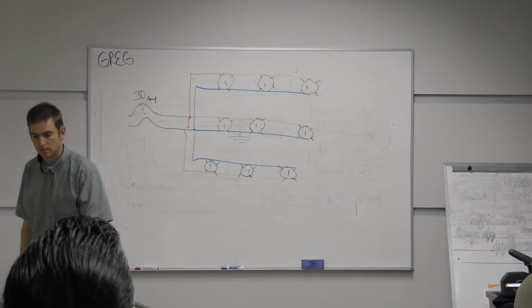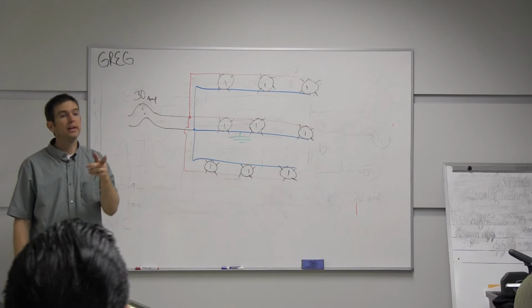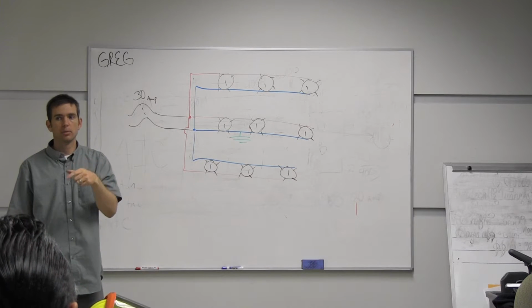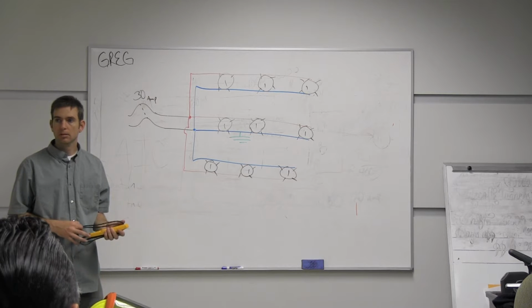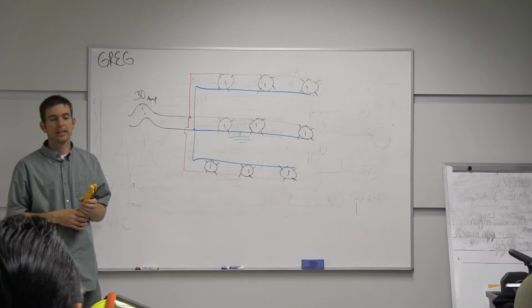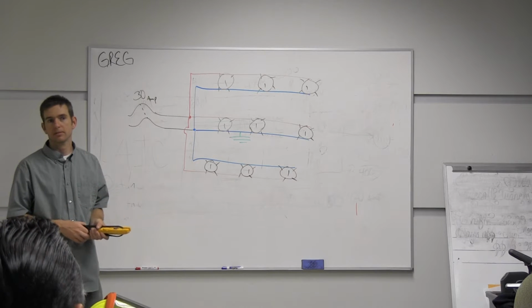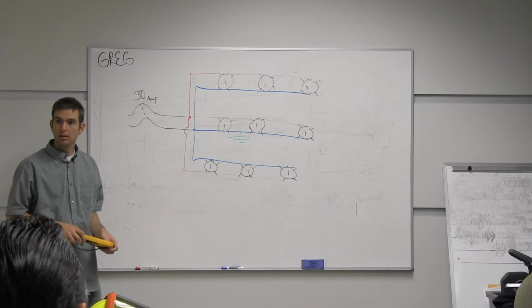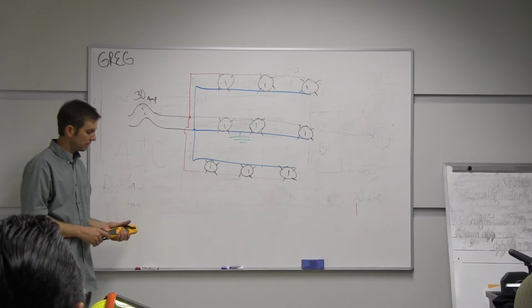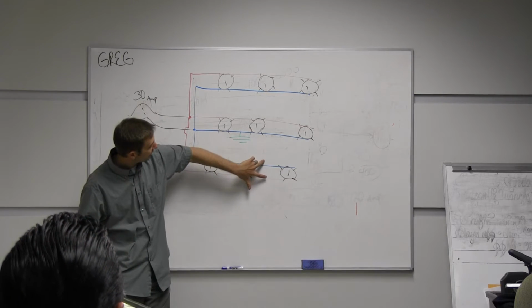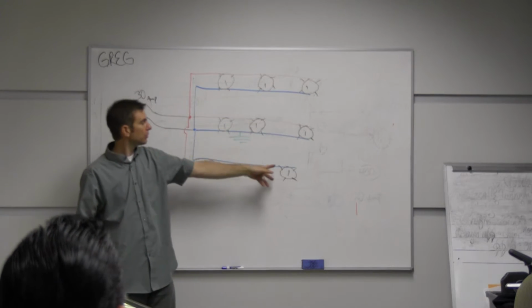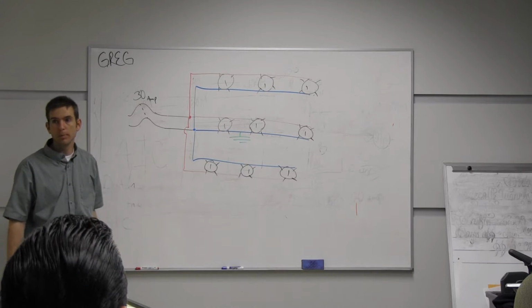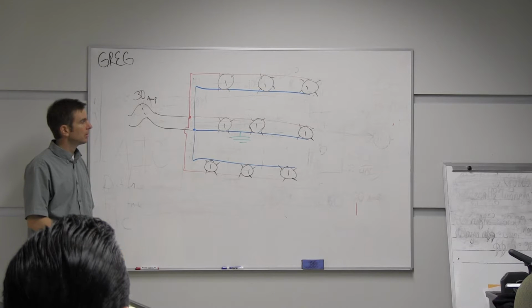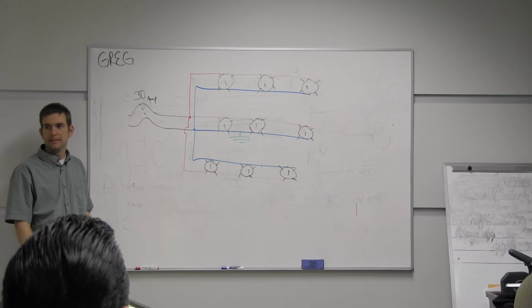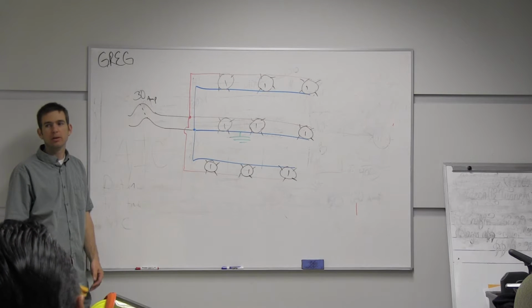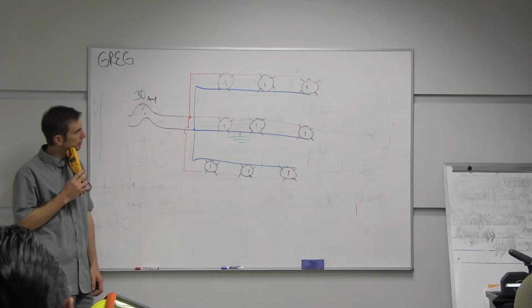So, what are some techniques we can use to determine maybe where the problem is? We check the 3 circuits one by one. That's an option. It's not my first choice, but it's certainly an option. What are some other ideas? The hint is it takes 5 seconds for it to trip. Check the furthest load from the breaker. Well, that's possible. That's an idea. But I can see here I have 1 leg, 2 legs, 3 legs. It splits off. So this one's the furthest, this one's the furthest, and this one's the furthest. So I've got 3 different options of what might be the furthest. But that's possible. What else can I do? Let's use Ohm's law and what we know about testers and what we know about the 5 seconds.